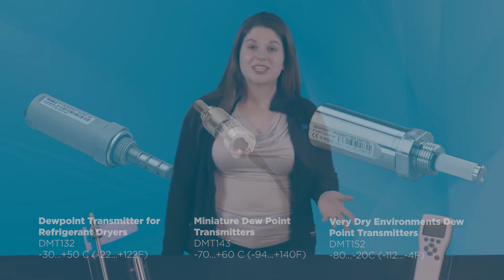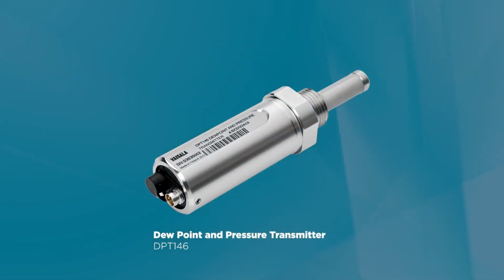In addition to these options, we also offer the DPT-146 combined pressure and dew point transmitter, which was specifically designed for compressed air applications. This transmitter is a unique 2-in-1 solution that includes an integrated pressure sensor to provide both pressure measurements and live pressure compensated dew point measurements.